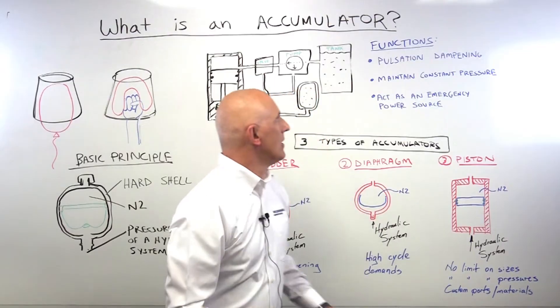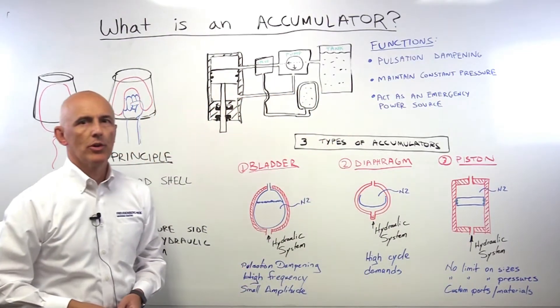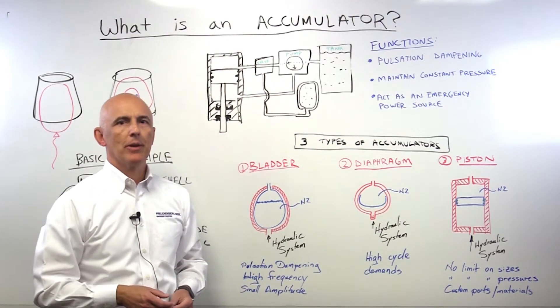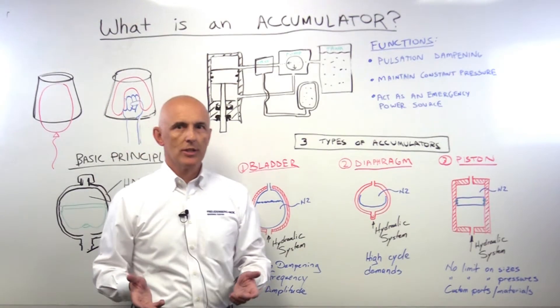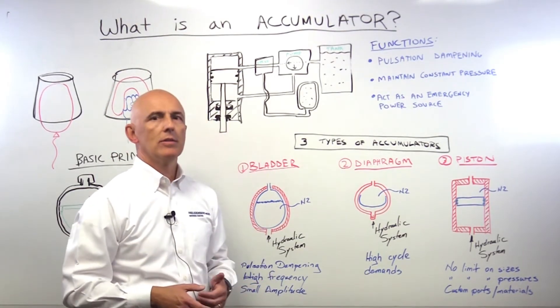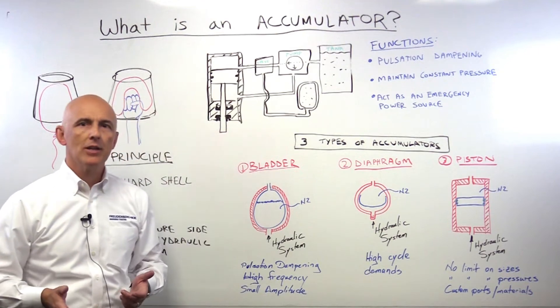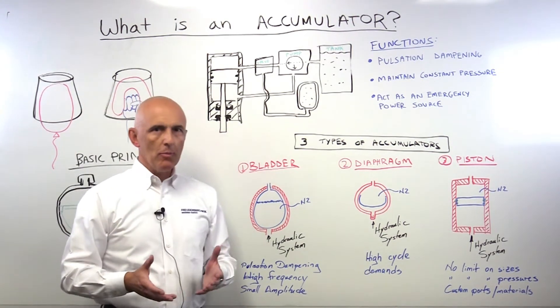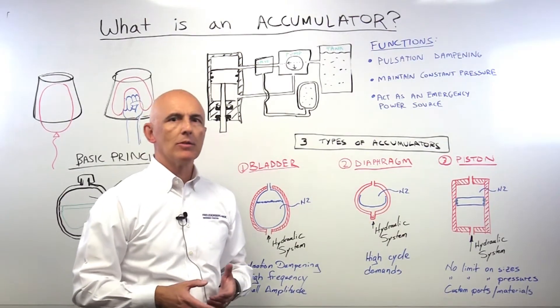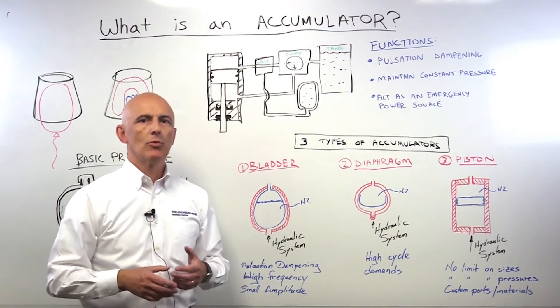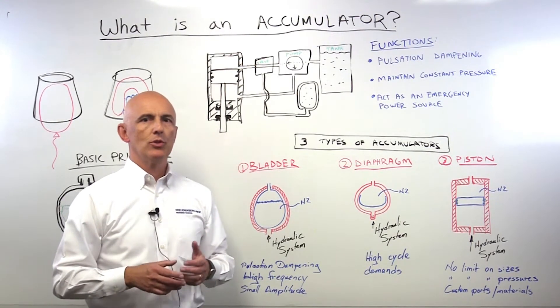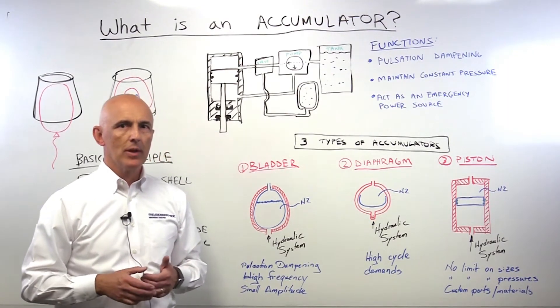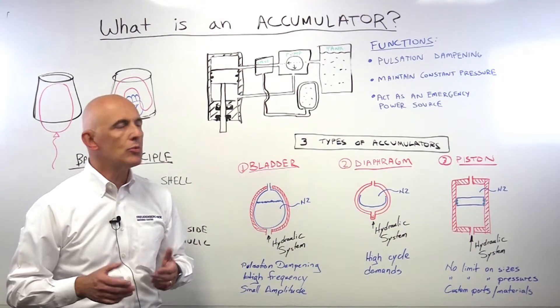This brings us to the basic functions of the accumulator, starting with pulsation dampening. On the hydraulic system, you have pulsation coming basically from the hydraulic pumps. The accumulator will dampen this pulsation and stabilize your system. So you reduce the noise, you reduce the vibration of the system, and you have the system working smoothly.